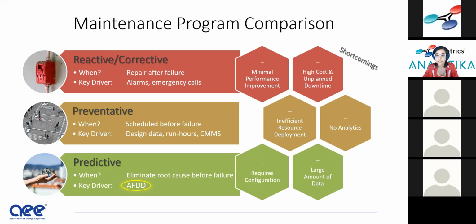When equipment is installed in a building, designers will take note of component lifetimes, operating hours, wear parts, rated cycles, lubrication, etc. Usually run hours is the key driver for when maintenance activities should be performed. So you're not optimizing when you're performing these maintenance activities, but ideally the perfect preventative maintenance program would schedule all of this maintenance so that no failure occurs. Of course, that's not found in practice to be true, but you can help automate the preventative maintenance program through a computer maintenance management software package, a CMMS software package.